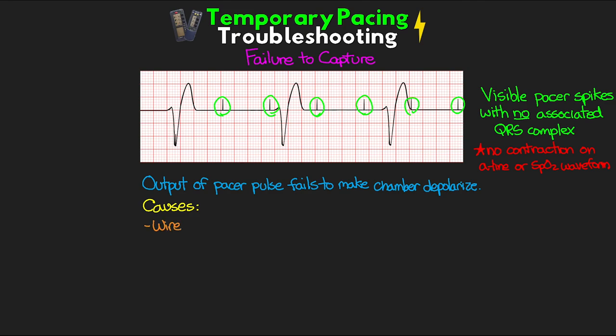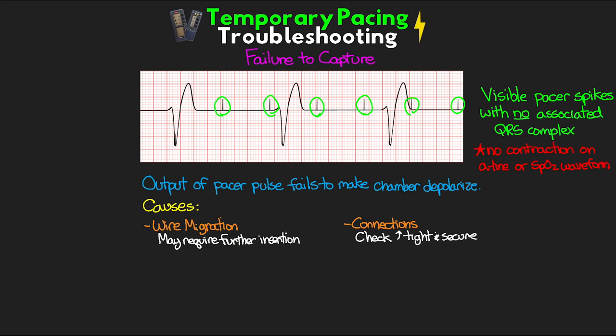Recognizing failure to capture isn't that difficult, but understanding the causes so you can fix it is what's important. First, wire migration — the wire may have moved from the proper placement and may require the provider to insert it a bit more. Second, check your connections — ensure they're tight and secure, because loose connections may prevent delivery of the full electrical energy set at the output. Third, the output itself might not be high enough, so increase the milliamps until you achieve capture, then determine the stimulation threshold and set to a two-to-one safety margin.